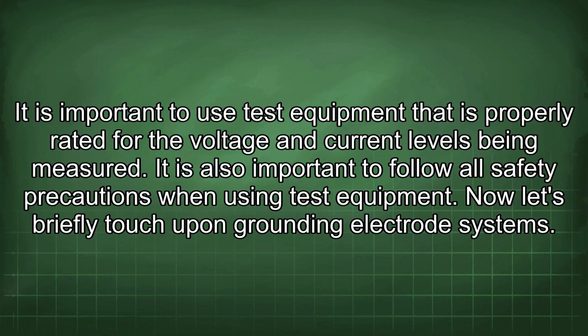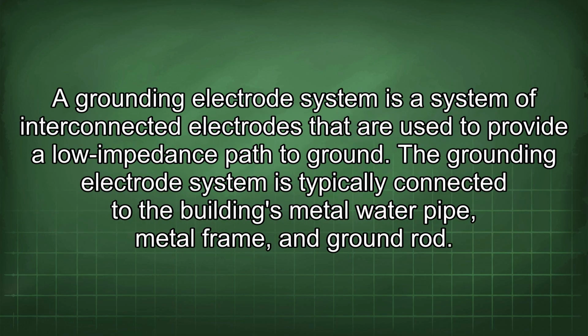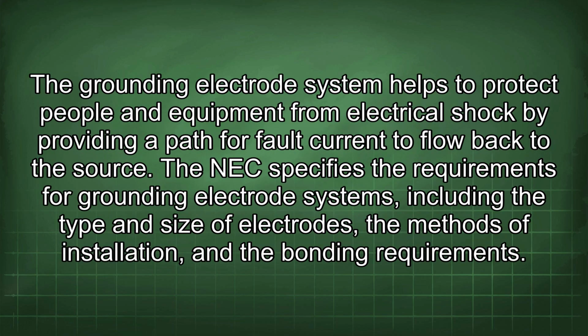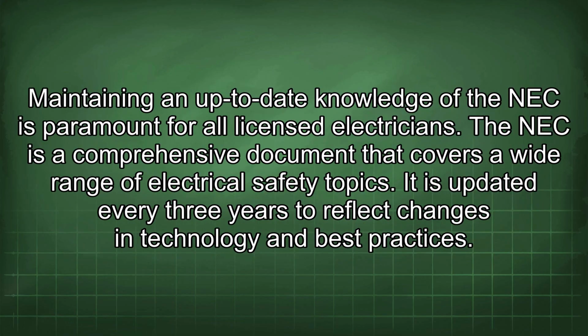Now let's briefly touch upon grounding electrode systems. A grounding electrode system is a system of interconnected electrodes that are used to provide a low impedance path to ground. The grounding electrode system is typically connected to the building's metal water pipe, metal frame, and ground rod. The grounding electrode system helps to protect people and equipment from electrical shock by providing a path for fault current to flow back to the source. The NEC specifies the requirements for grounding electrode systems, including the type and size of electrodes, the methods of installation, and the bonding requirements. Maintaining an up-to-date knowledge of the NEC is paramount for all licensed electricians.